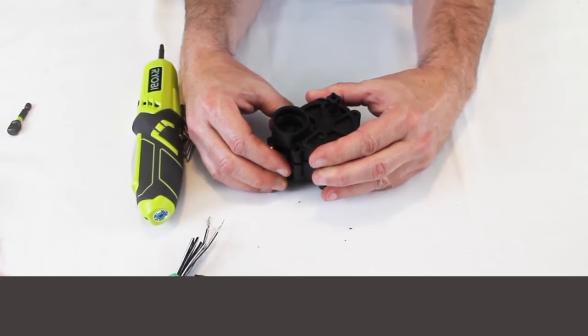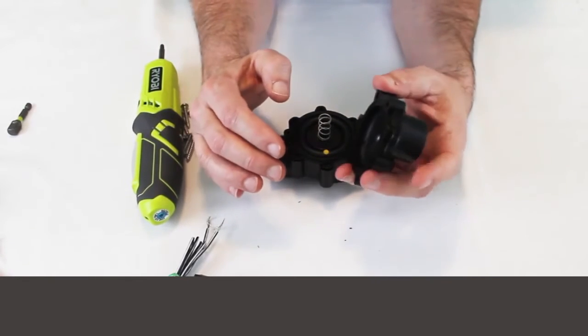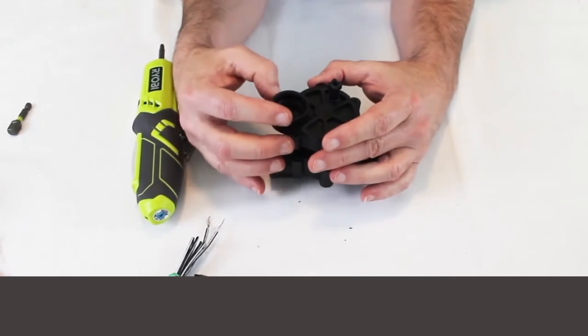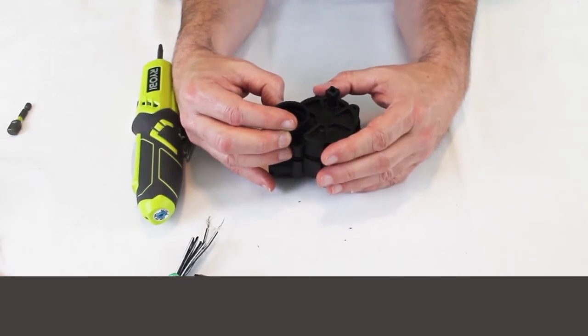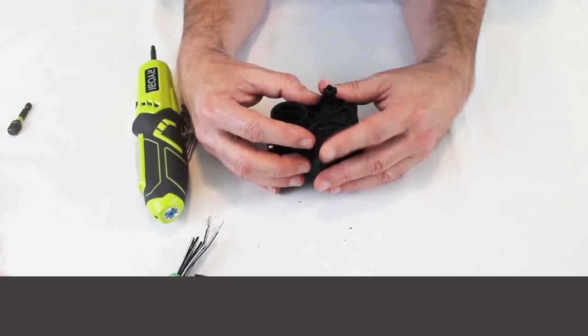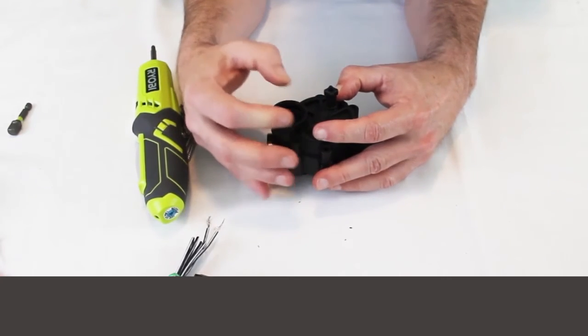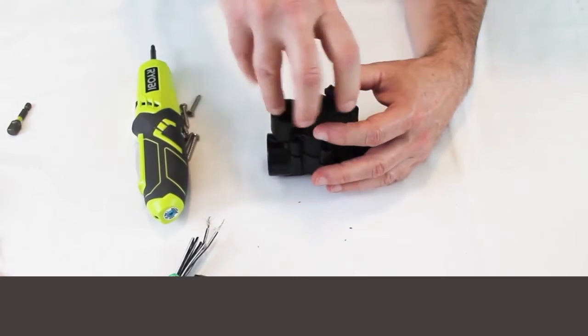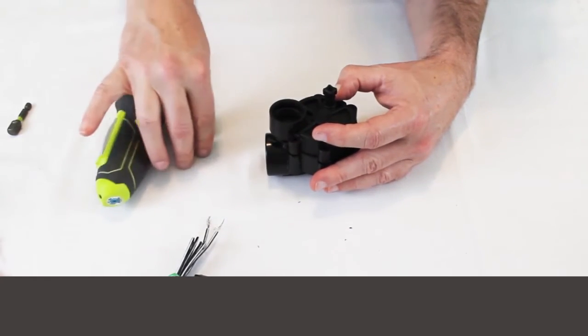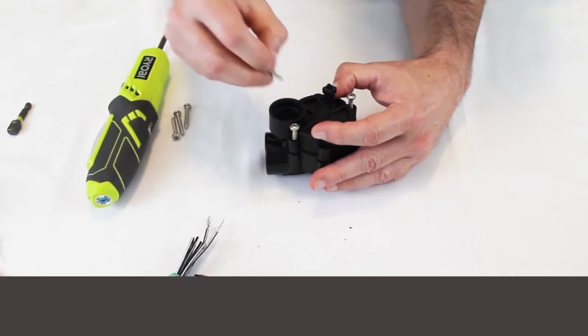The thing is on this one, on other valves it's kind of hard to get it out of a line, but on this one you have to just make sure that you're putting this down here in the right place. The screws are going to line it back up, but it's a lot better if you put it back down and you're pressing straight down on it versus trying to move it around or spin it around, which may cause the diaphragm to come unseated. So let's put this back together.